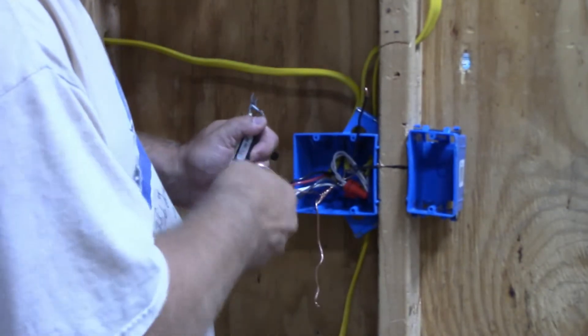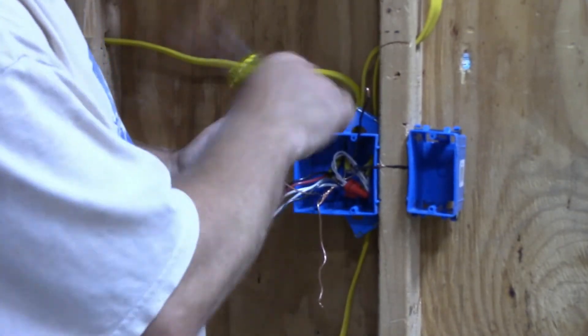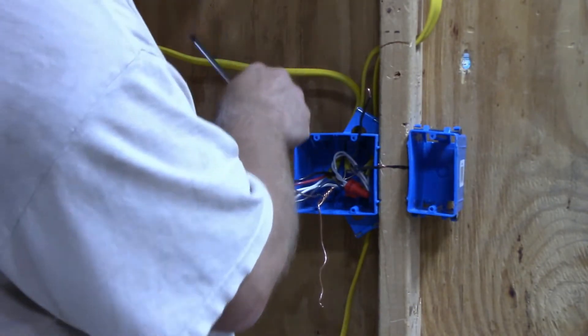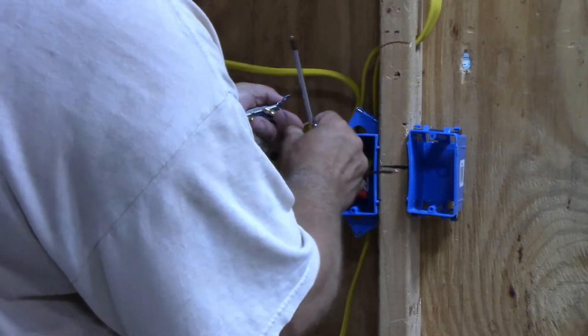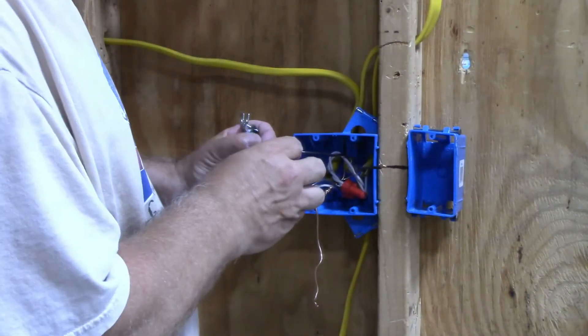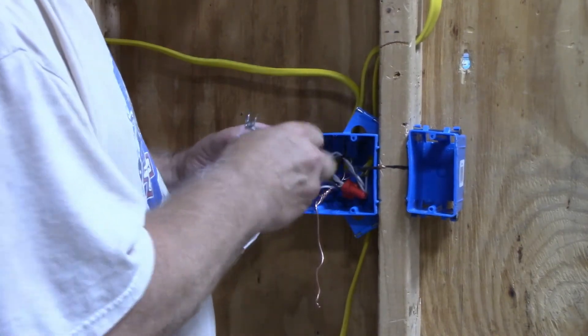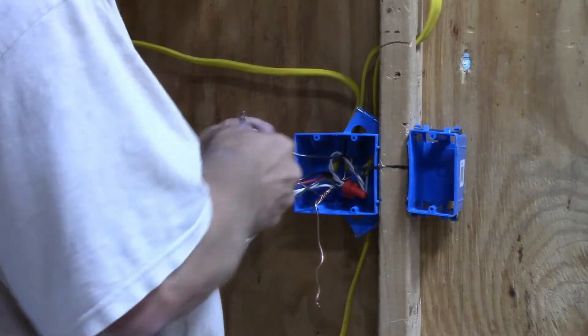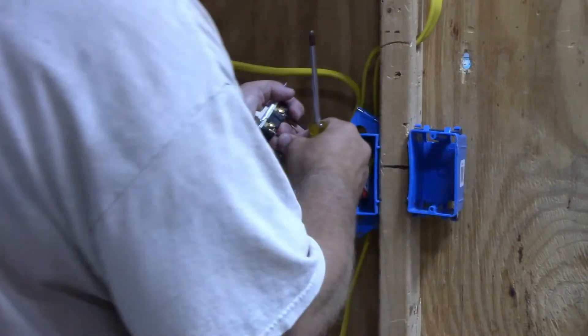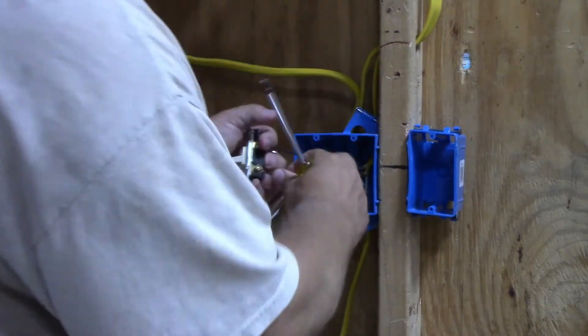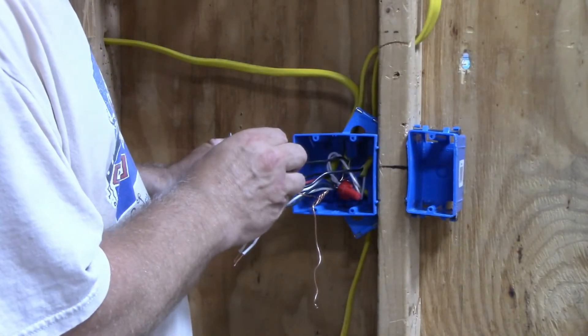Always put the hook in the direction in which you're spinning your screw. The other two, it does not matter which one gets the hot and which one gets the switch leg, since it's a single pole switch. It's either on or off. I'm going to put the hook in the direction in which I turn the screw.